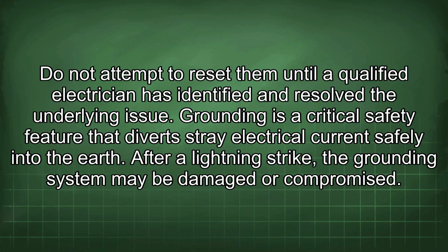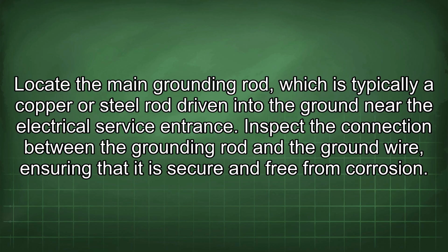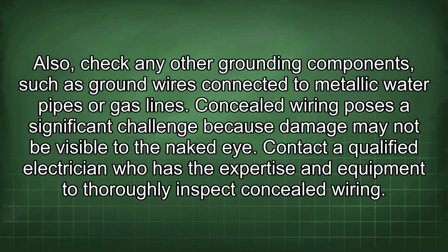Grounding is a critical safety feature that diverts stray electrical current safely into the earth. After a lightning strike, the grounding system may be damaged or compromised. Locate the main grounding rod, which is typically a copper or steel rod driven into the ground near the electrical service entrance. Inspect the connection between the grounding rod and the ground wire, ensuring that it is secure and free from corrosion. Also, check any other grounding components, such as ground wires connected to metallic water pipes or gas lines.